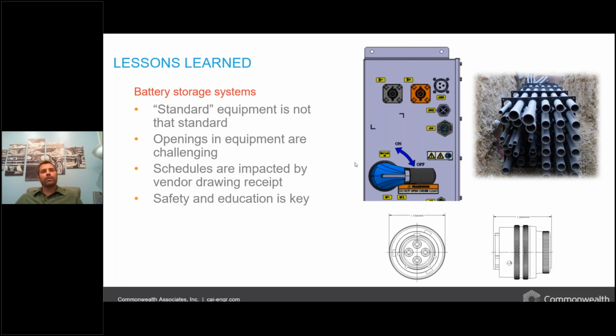Number two, equipment openings are often bottom fed and very small. So the electric code determines how many conductors and the size of conduits we need, and they don't always fit so well. At least they do fit on paper, but it's hard to do in the field because it's very tight. And then I mentioned the schedule earlier. Schedules are often adjusted for any project, and BESS projects are no different. A consideration here is that a BESS project may appear pretty straightforward as I walked around the major piece of equipment, but there's a lot of little details to consider. And with the EPC contracts mentioned earlier, there can be penalties for missing an in-service date.